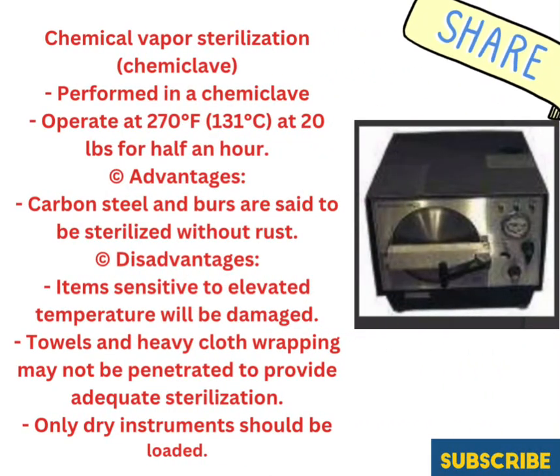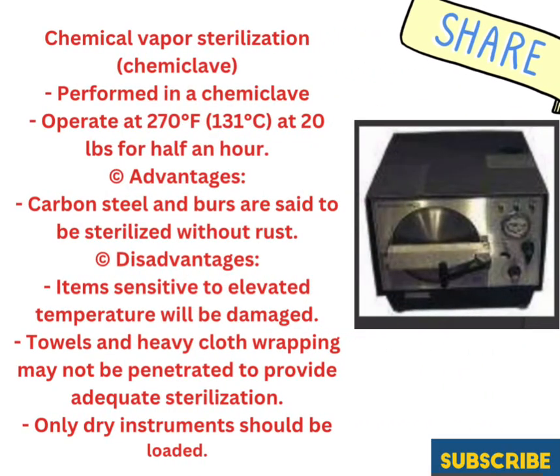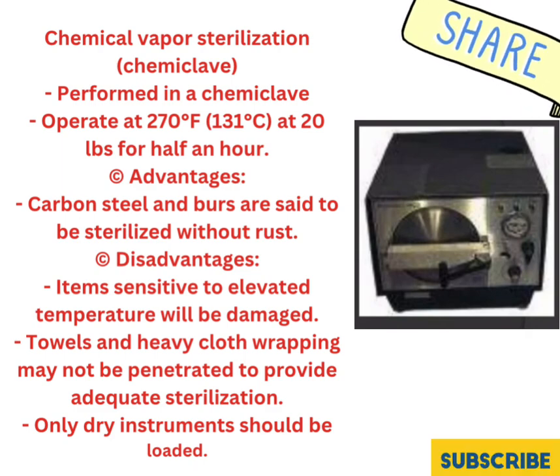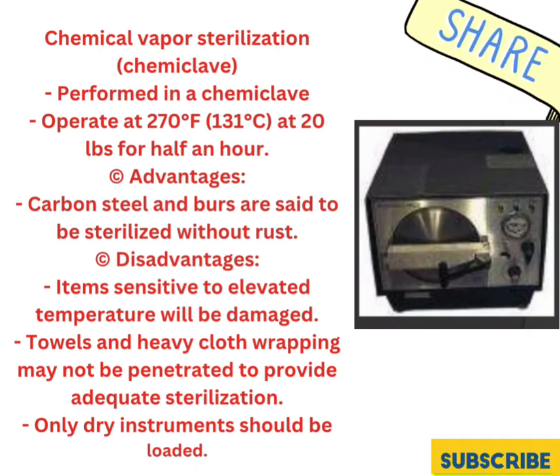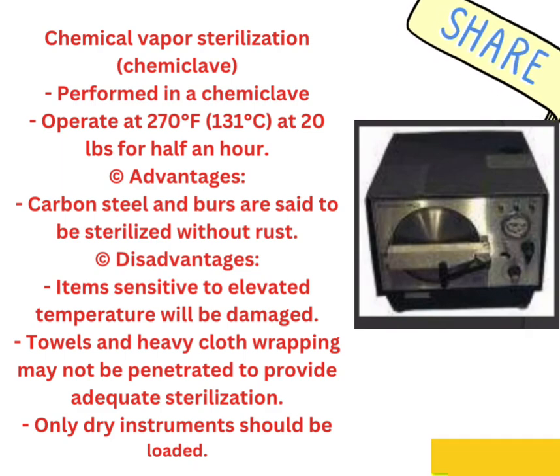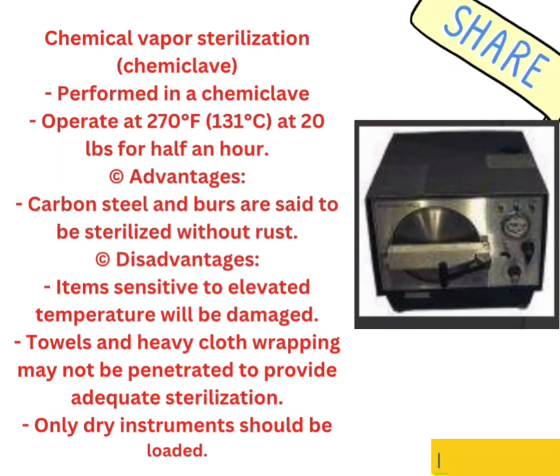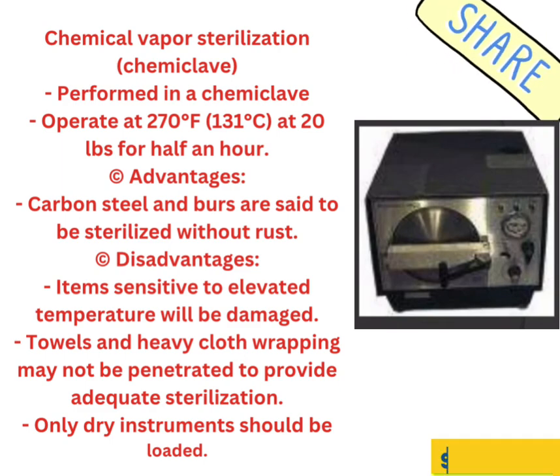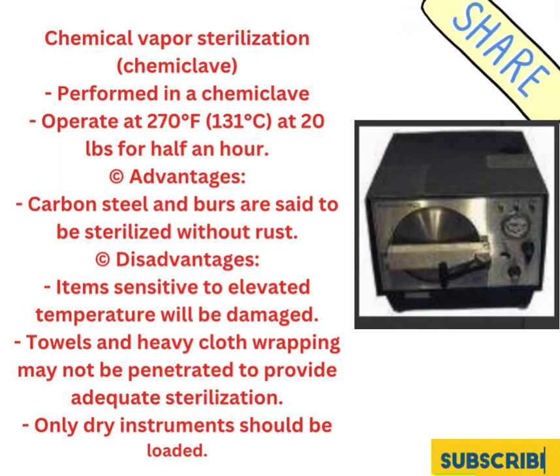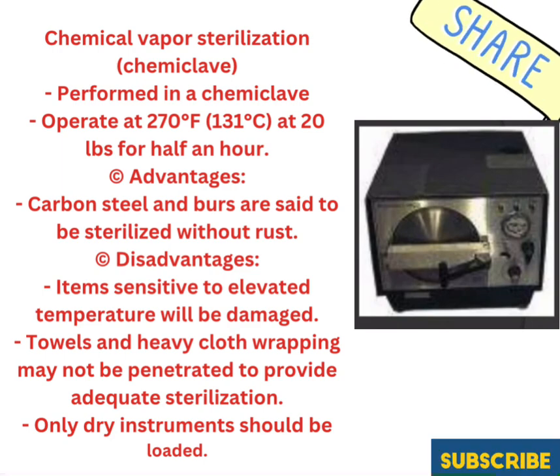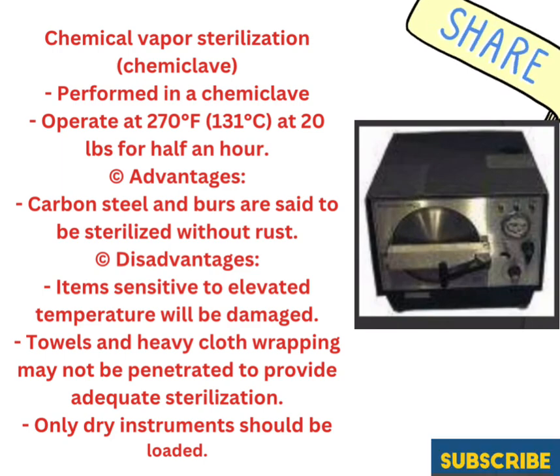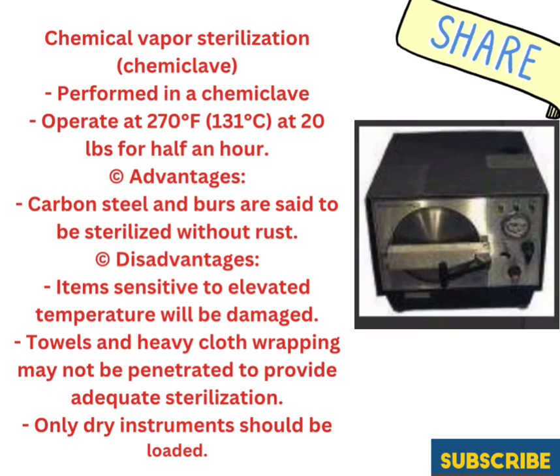Chemical vapor sterilization, chemiclave. Performed in a chemiclave. Operates at 270 degrees F, 131 degrees C, at 20 lbs for half an hour. Advantages: carbon steel and burrs are said to be sterilized without rust. Disadvantages: items sensitive to elevated temperature will be damaged. Towels and heavy cloth wrapping may not be penetrated to provide adequate sterilization. Only dry instruments should be loaded.